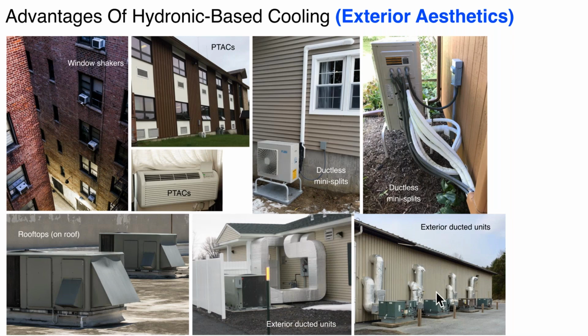Here's one of my favorites. These are exterior air-to-air heat pumps. You can see the ducting going in the building, and you'll notice they're installed right under a metal roof. So again, this is actually up in the southern Adirondacks in New York State. That roof could easily have 2 or 3 feet of snow on it. And when that slides off of there, that doesn't bode well for the ducting or the heat pump. So, with a hydronic system, we can make much of this go away and improve the building aesthetics.